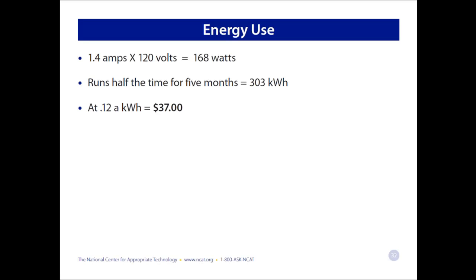They're very low amperage. The unit that I installed drew 1.4 amps, and that amounts to 168 watts when it's running. And I estimated that it would run about half the time for the 5 month period that it was installed and running for this project, which amounts to 303 kilowatt hours of usage. And based on a 12 cent kilowatt hour, that comes to $37 to run the unit for 5 months.